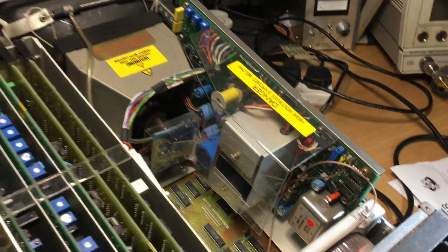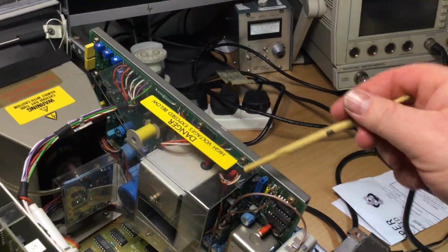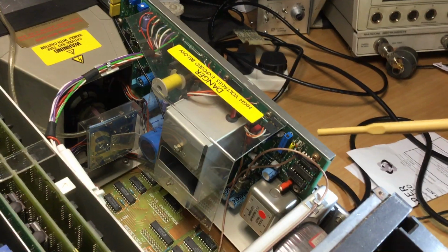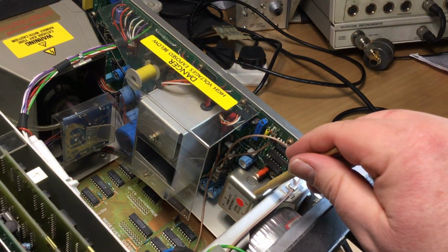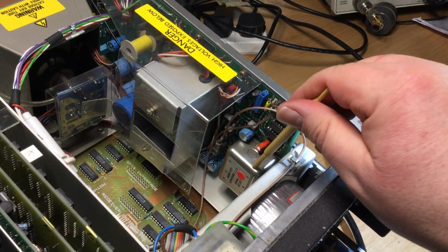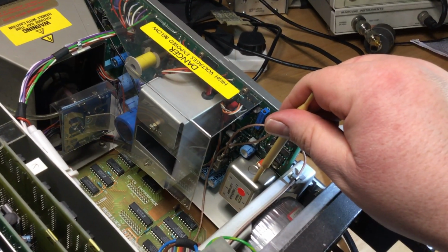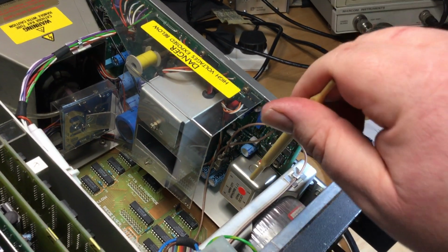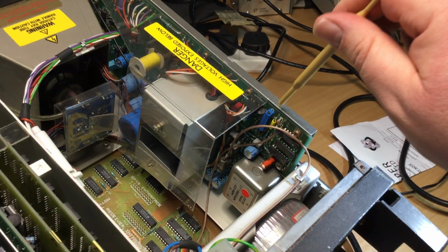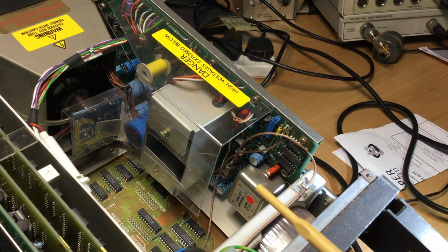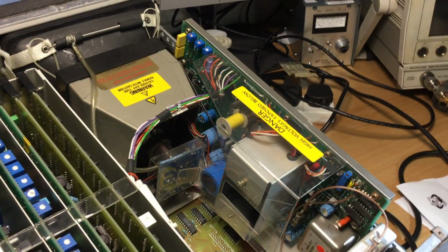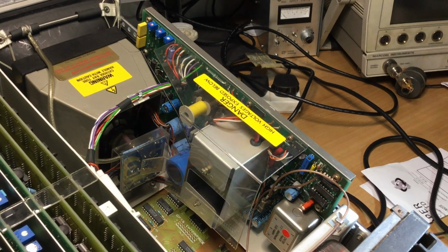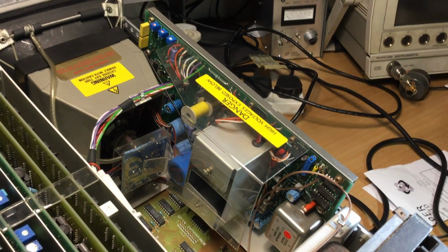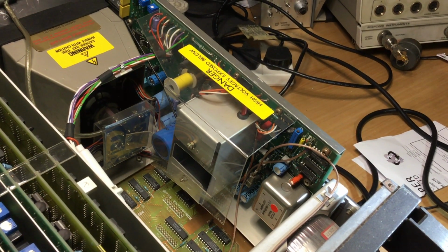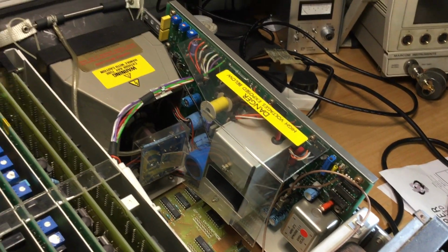Obviously the monitor, the CRT monitor, is driven off of this board here. This board serves two purposes. One is for the instrument's temperature controlled crystal oscillator, which gives a frequency accuracy of the instrument, and that can be adjusted with various potentiometers. So if you're setting this test set up to work accurately against another known reference, for example, you can calibrate that TCXO against that instrument, and then obviously you can calibrate the frequency accuracy of the instrument.